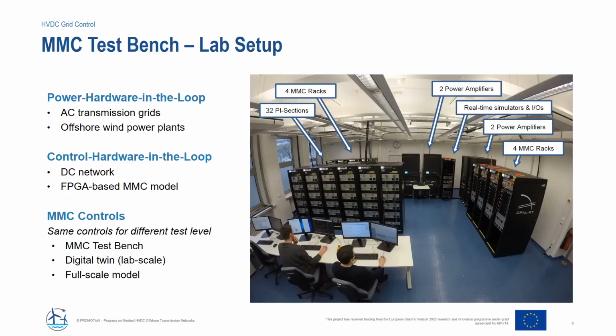Overall, we can use the system in a power hardware or control hardware in the loop approach. In the power hardware in the loop approach, the DC grid is represented physically in small scale. The AC transmission grids and offshore wind power plants are embedded in a real-time simulation. If we use the control hardware in the loop approach, all the electrical parts are simulated in a real-time simulator, and the MMCs are simulated using an FPGA-based model, but we can use exactly the same controllers also for this real-time simulation, so the physical MMC controllers. And this is a very important aspect for us.